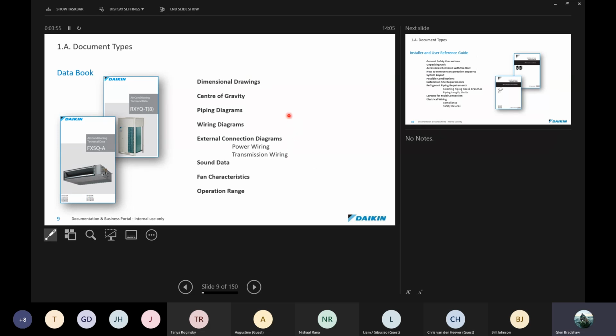Some more information that's in there includes center of gravity, which will help when it comes to lifting equipment, some piping and wiring diagrams, and so on, right through some sound data, and then also the operational range of the unit. Very, very important documentation. And it's a good idea that you actually have this documentation for all the equipment that you're installing at the time of doing a VRV installation.